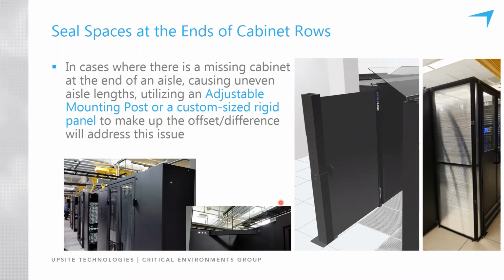Depending on how subtle, like a few inches, or how dramatic, like maybe a whole tile or more, this offset might be, there are a number of ways to accommodate the scenario. If structural rigidity of the door needs to be considered, then added bracing may be needed in addition to just sealing the gap. What you've got going on in these pictures, in the bottom left inset, is another co-location environment. It's a wide aisle. You've got a cabinet on the left with 48-inch wide dual swing doors, and then probably another foot to 2 feet of open aisle. And then this thing returns back.